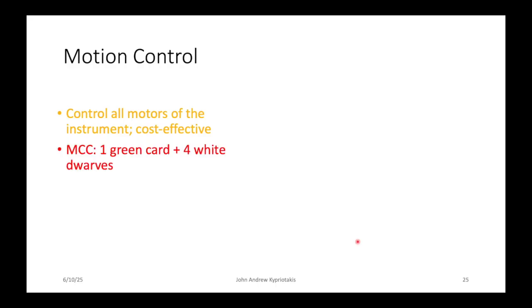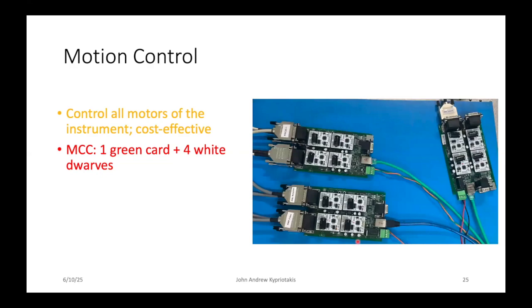Let's move on now to how we control the motion of the instrument. All the motors need to be controlled cost effectively, and that's both in power and in optics. We need to not have any optical parts within the motor control, such as light switches. To do that, we have what we call motion control cards, which are comprised of one card called the green card and 4 white dwarfs on each card. And this is shown here where you see the green card and the 4 white dwarf cards on it.